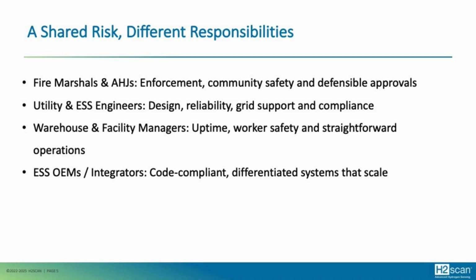But also, fire marshals and authority having jurisdiction personnel also have the responsibility for enforcement and keeping the community safe, and making sure that we have defensive systems so that we are protecting people and protecting buildings. But the engineers that design these spaces also have a responsibility to make sure that they're following current codes and regulations and best practice standards, and that they are in compliance with the current regulations. This also means that it's not a one-size-fits-all. So you could have a charging area in a very wide space and meet the 25% lower flammability level or 1% of hydrogen requirement and be fine.